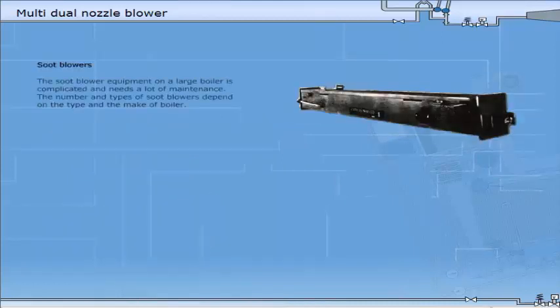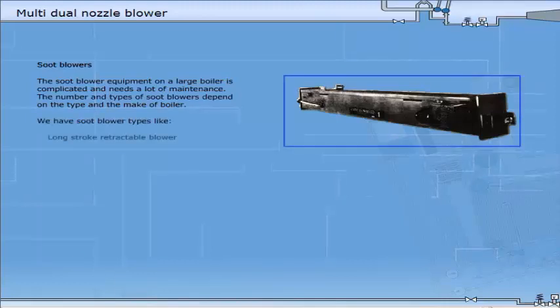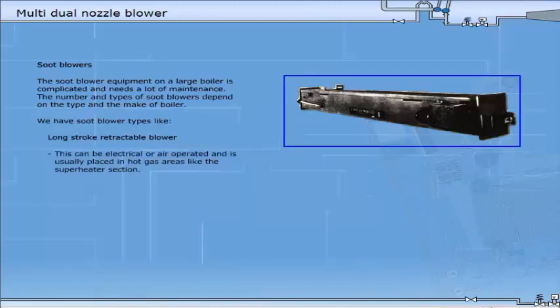The soot blower equipment on a large boiler is complicated and needs a lot of maintenance. The number and types of soot blowers depend on the type and the make of the boiler. We have soot blower types like a long stroke retractable blower. This can be electrical or air operated and is usually placed in hot gas areas like the superheater section.